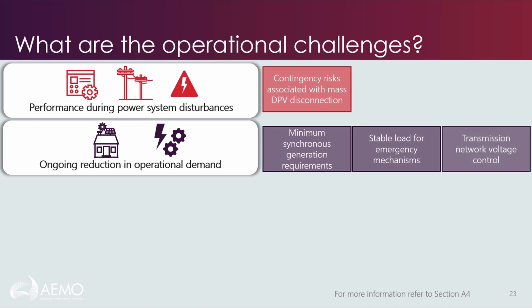The next impact DPV has on the power system is the ongoing reduction in operational demand. This is simply that more DPV erodes the operational demand during the middle of the day. This in fact presents some key challenges as there are limits in the power system to minimum operational demand. This includes requiring a minimum level of synchronous generators online for other system services that cannot be served by DPV. Also, for our emergency mechanisms that are utilised following a sudden event, we require a minimum level of stable load online. Otherwise, these protection schemes may not operate as they were intended.